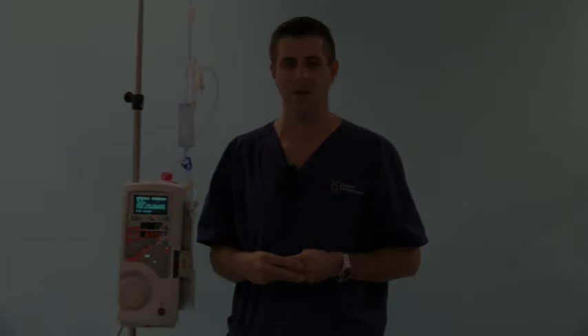So that's giving you the most accurate reading, but it's also going to be the most affected by drops in the patient line as the fluid sits there for long periods of time. And you'll see your temperature will rise up to that target as you're bolusing and running at normal to high flow rates, but it will drop at those very low flow rates. The next thing I'd like to talk about is preventing spills with the unit and preventing damage to the unit during spills.